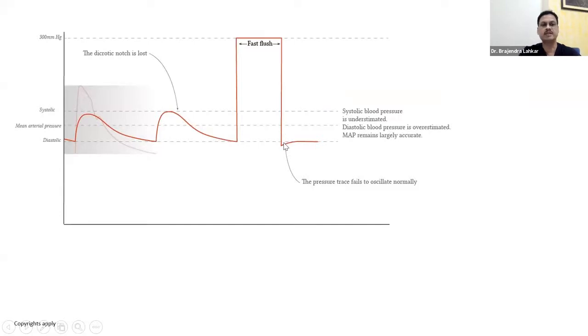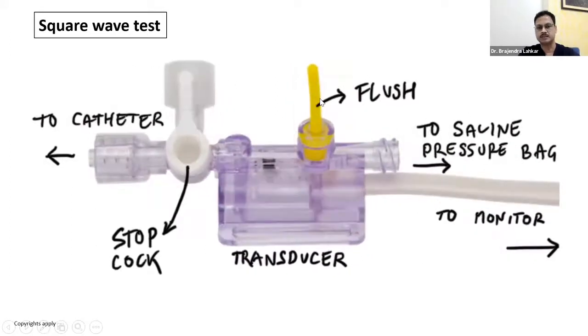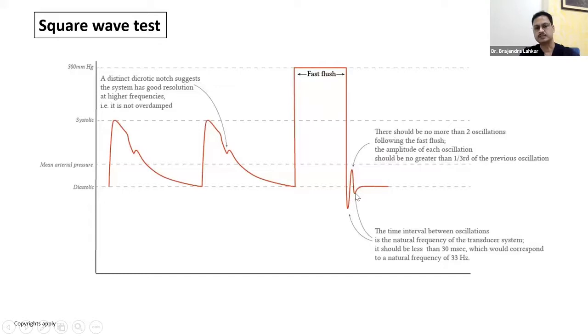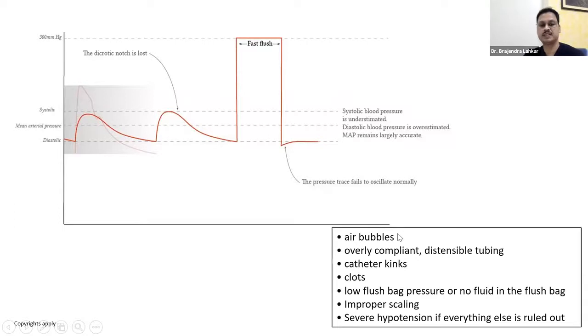Overdamping occurs when there are air bubbles in the system, when the tubing is overly compliant and distensible rather than rigid, when the catheter is kinked, or when there is a clot inside the system blocking flow. When you observe an overdamped or flattened waveform, you must investigate these causes and correct them before trusting the pressure values being displayed. Ensuring a rigid, non-compliant tubing system free of air bubbles and clots is essential for accurate arterial pressure monitoring.